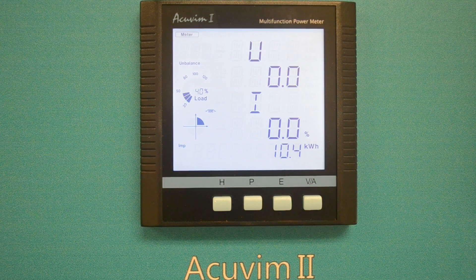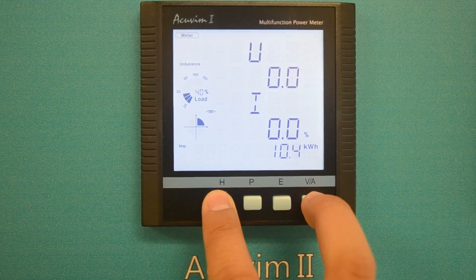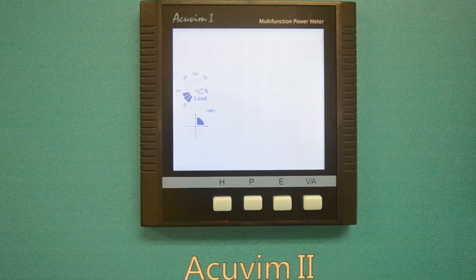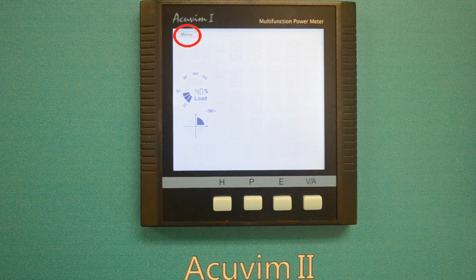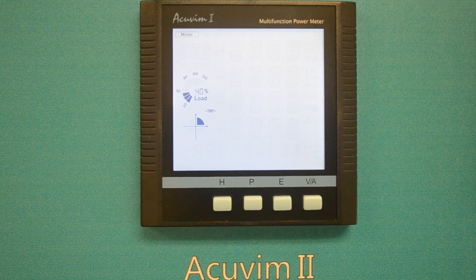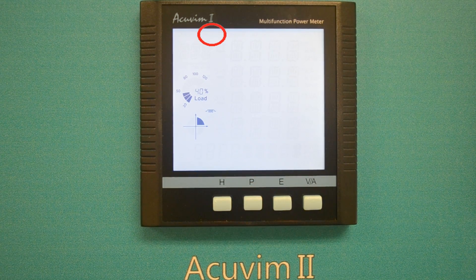We will now move on to reading the max and min record. Press the H and VA key simultaneously, holding them for about 1 second. The main display section will become blank and you will see the meter icon flashing in the mode display section. Press the P key to move the flashing icon to max and min, then press the VA key to enter the max and min mode.